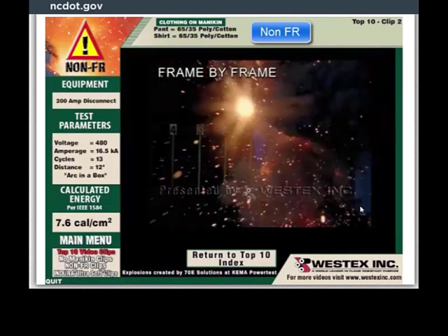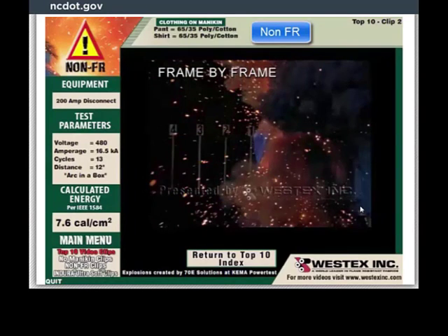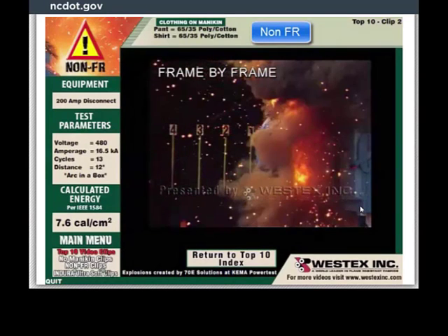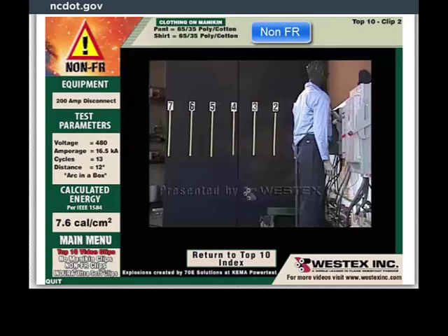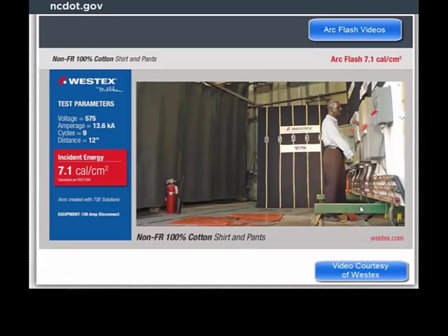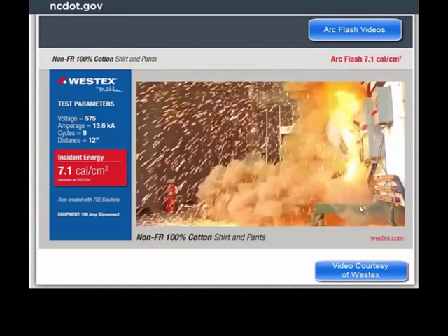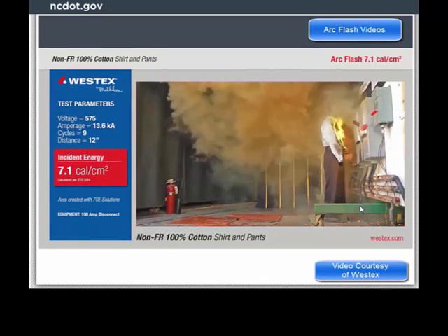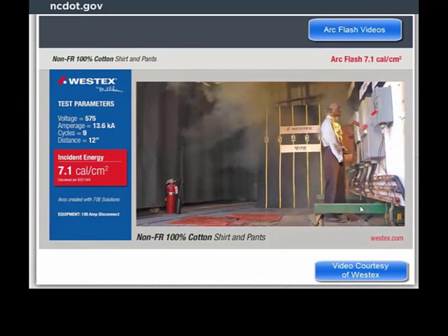And again, that's 22 feet from the arc. So the molten metal is obviously a significant hazard at a great distance from the arc. This mannequin is wearing 100% cotton, non-flame resistant shirt and pants. We have an arc and a resultant clothing fire. The pants didn't quite ignite, but the shirt certainly did.